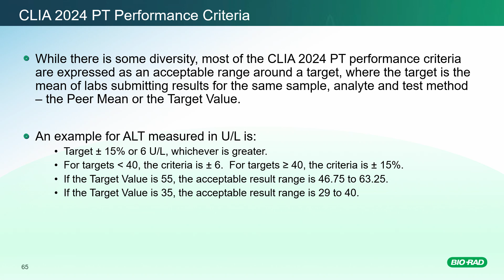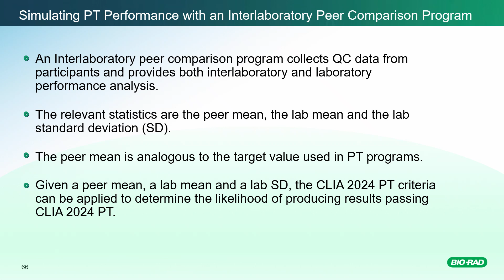And when we think about that, this is very similar to what we're doing with interlaboratory peer comparison, where we're collecting data from many labs that are using the same lot number of QC and the same test method, and we're developing peer statistics, including the peer mean. That's the most critical thing, which would be analogous to the target in a PT performance program. The other 2 relevant statistics that we need are the lab mean and the lab standard deviation. So if we've got a peer mean, a lab mean, and a lab SD, well then we can apply the PT performance criteria to determine what's our likelihood of producing results that would fail the CLIA 2024 PT specifications.